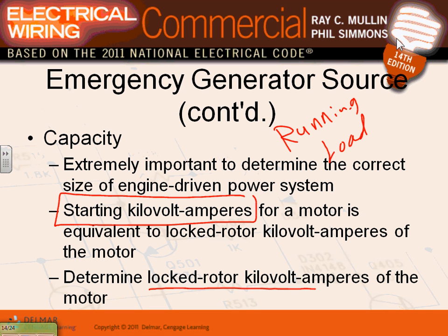If you remember the software that we have, we put all the stuff that we did in one step, and we came up with this size generator. If we actually put them in different steps, meaning we start them at different times, 10 seconds, 10 seconds, 10 seconds, staggered, then your generator comes out at a smaller size.